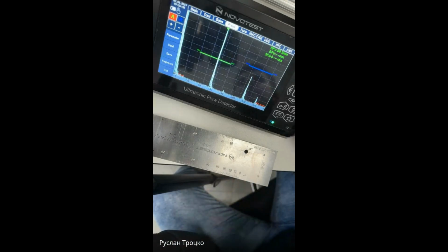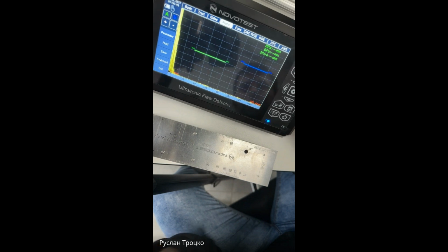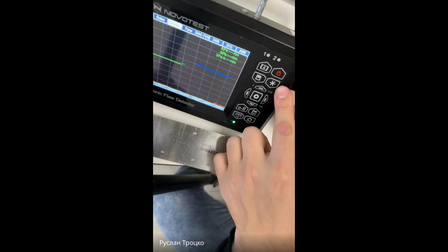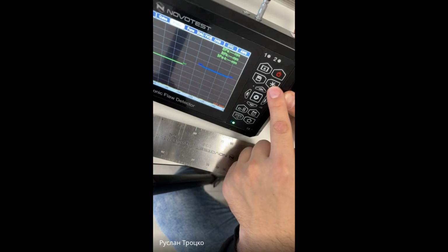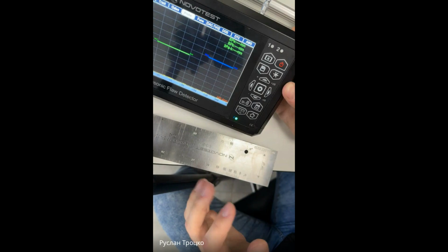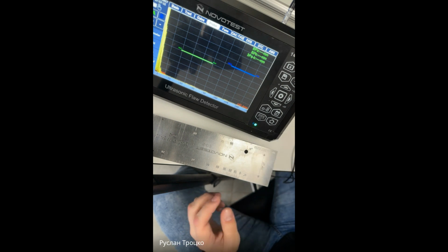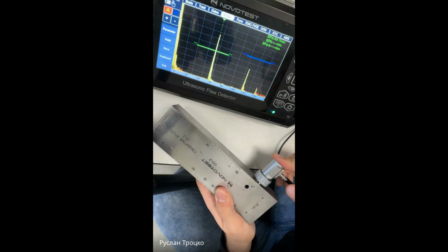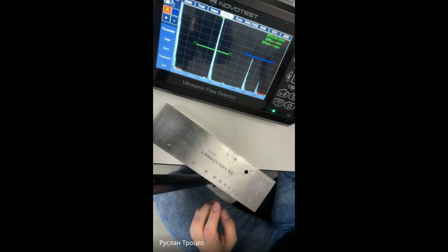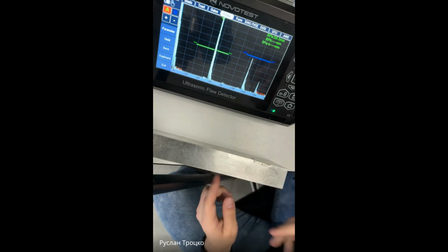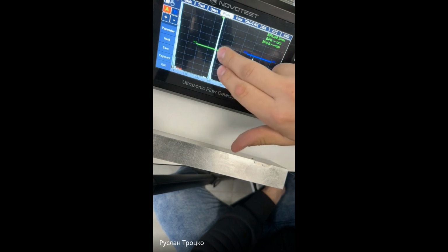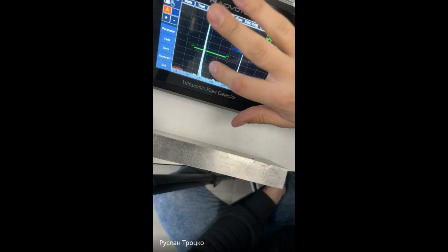I have a life hack for you. On the keyboard, you have this button. It's a freeze button. You can freeze your picture and remove the probe from the calibration sample. It freezes and you remove. Yes, and now you can remove the probe. You don't need to hold it. Let me show you. I get the signal. I freeze, and now I can remove the probe to analyze my A scan. Okay.